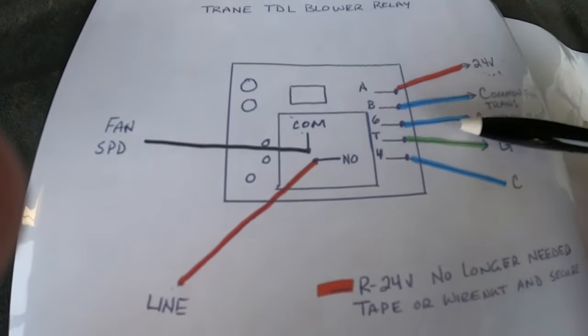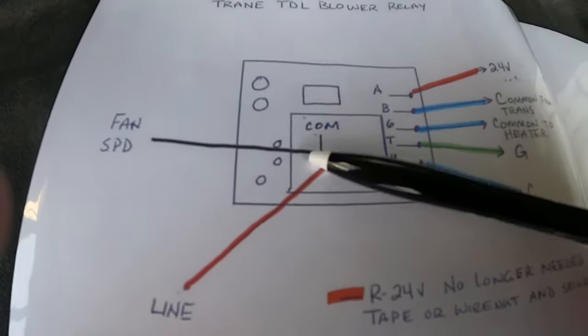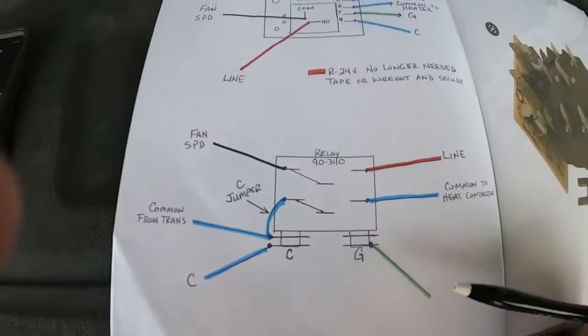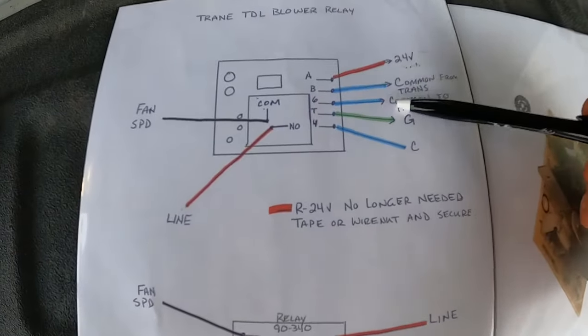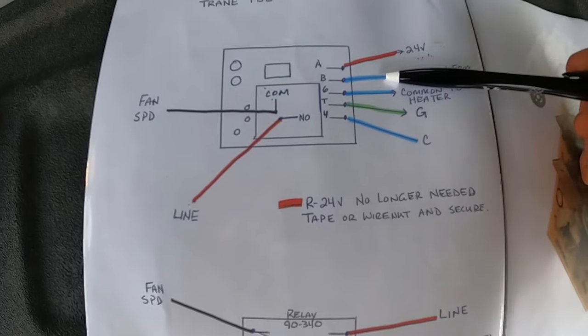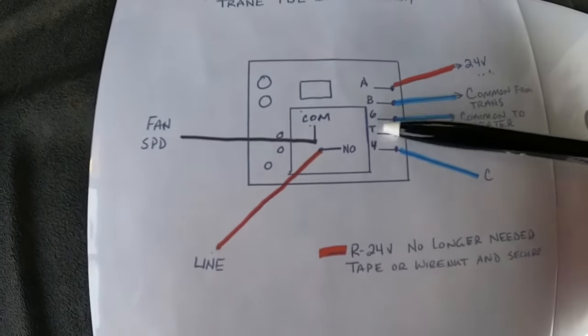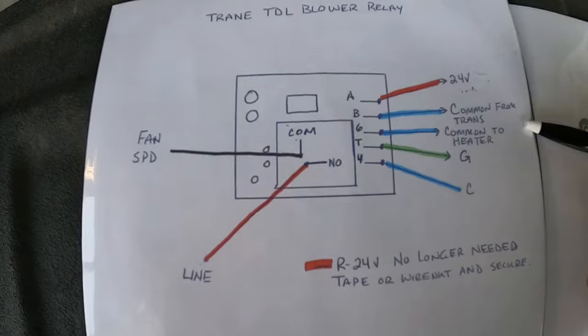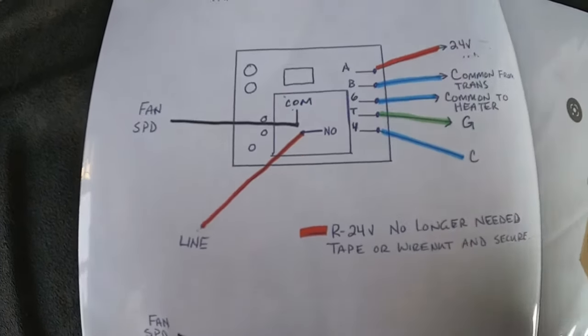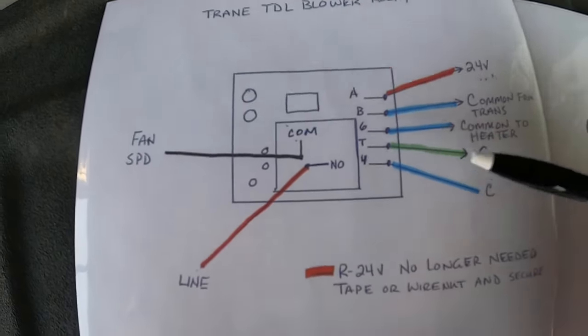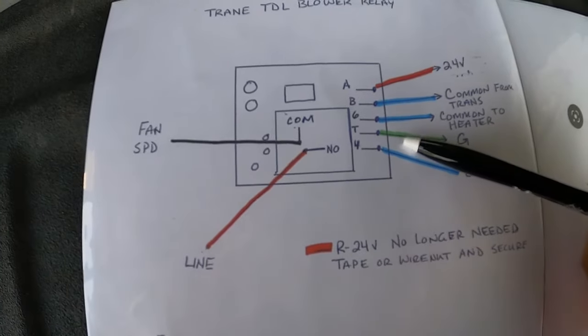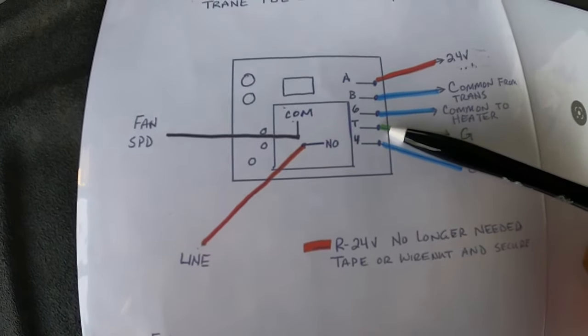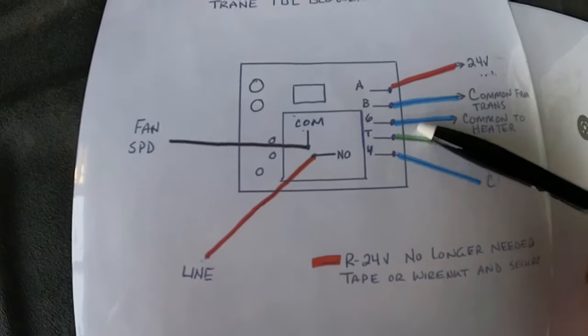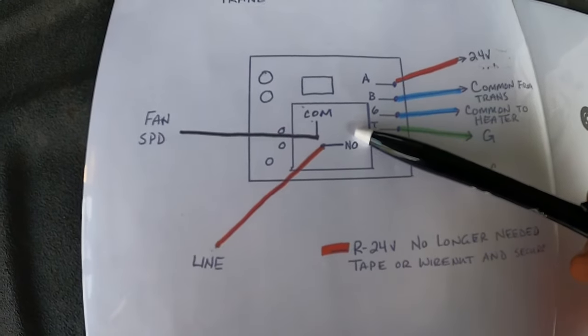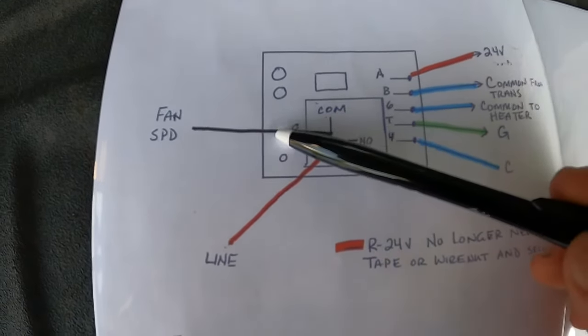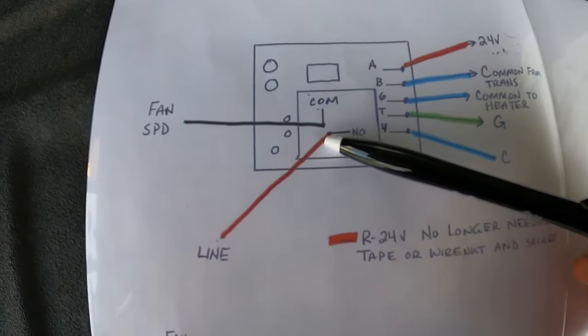Then it lays out where every other wire is going to go on this board. We'll start with your commons. You've got 3 commons here. You got your common coming from your transformer. You got your common that goes back to your heat strips, and I'll explain that in a minute. You got your G from the thermostat. So you get your call for your air handler blower. It's going to close this relay. It's going to have a time delay. But you got your common, which is your fan speed, and you got your line voltage in.